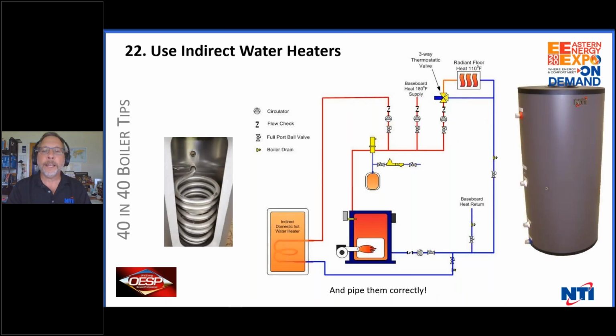Use indirect water heaters. Yeah, get rid of those coils. Take out that L8124 and put in an L8148. Get rid of the coil and put in an indirect water heater. That way the boiler can sit idle until they need hot water to be made back in the tank. Indirect water heaters have less than a 0.5 degree drop in temperature an hour. They lose nothing. You can't even begin to imagine how long.